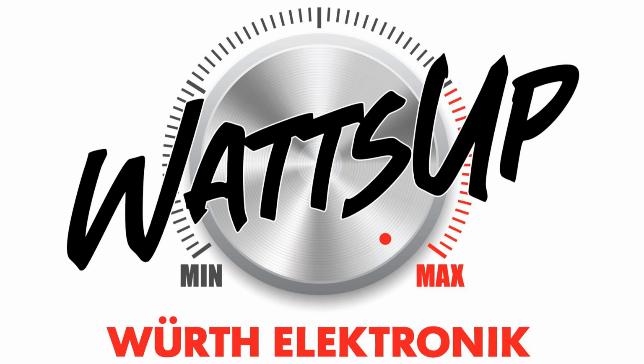So here, when you say that my sensor has accuracy of X percentage, then you also add some peripheral devices, for example, filters and amplifiers, which also add some noise and inaccuracy to your complete system. So at the end, sometimes you also have to recalibrate your whole system. The RTDs also might have the problem of self-heating, and they are also very design sensitive. So you have to take care of your design and invest a lot of time designing complex circuits.